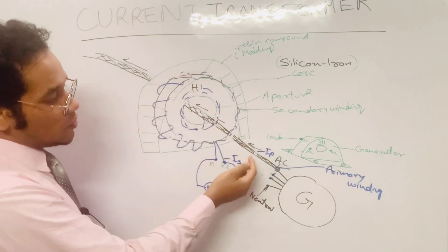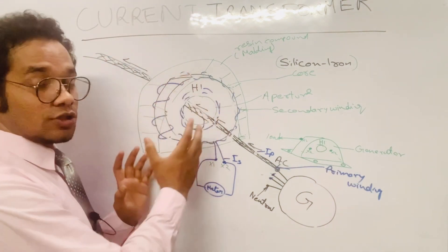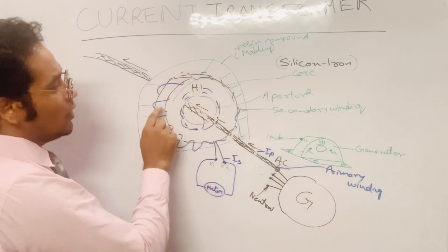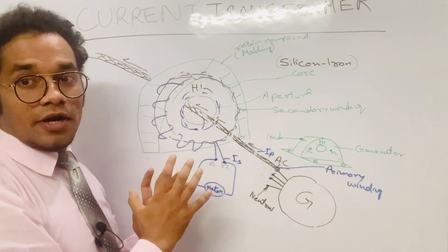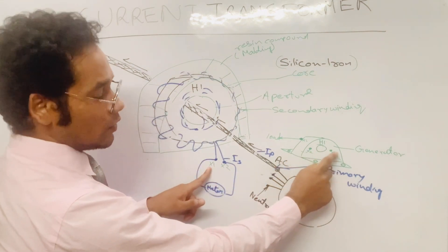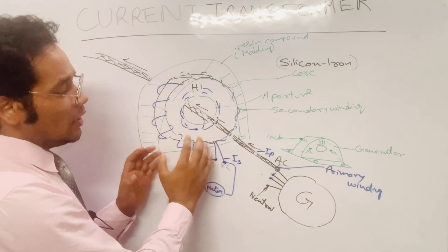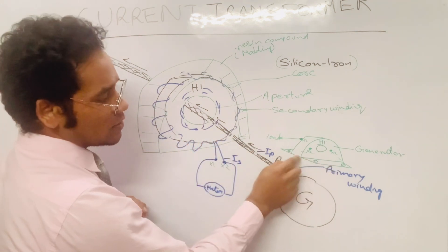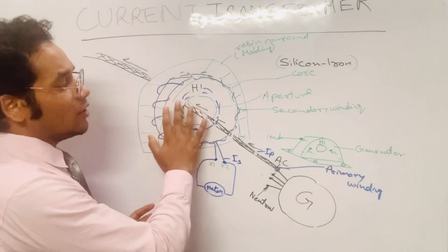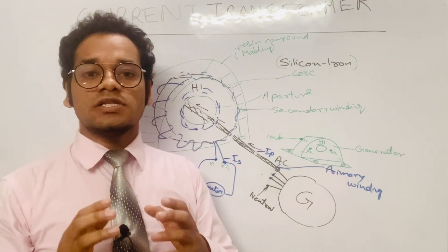To summarize: the current transformer is a device which can sense current for control, protection, and indication applications. Its construction consists of a toroidal-shape core made of silicon iron. On that core are the secondary windings — the current transformer consists only of secondary windings. The terminals X1 and X2 are used for output. The core and windings are enclosed within a casing or molding made of resin compound, placed on a metal base plate for mounting in the structure.